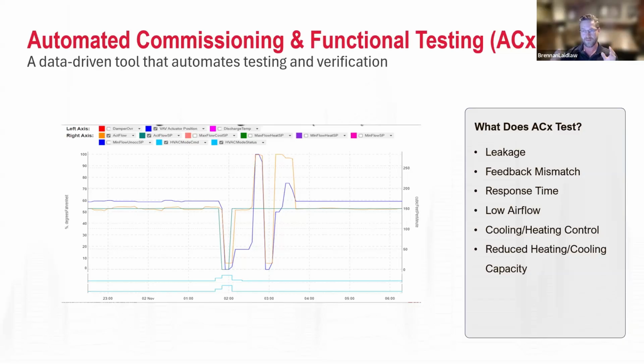So this is something I see as really beneficial for growth in terms of all the zones in a building, like all the terminal units, because even when we do a full commissioning of a building, usually it's a sample test after it's been commissioned. Not everybody goes through 100% tests. It might be a 10%, 20% test.